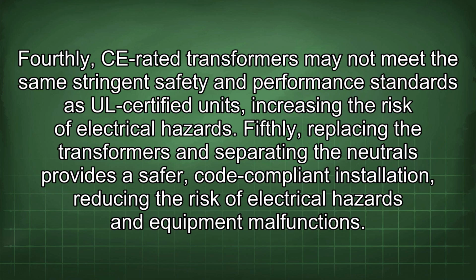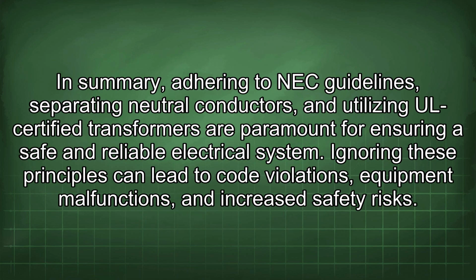Fifthly, replacing the transformers and separating the neutrals provides a safer, code-compliant installation, reducing the risk of electrical hazards and equipment malfunctions. In summary, adhering to NEC guidelines, separating neutral conductors, and utilizing UL-certified transformers are paramount for ensuring a safe and reliable electrical system. Ignoring these principles can lead to code violations, equipment malfunctions, and increased safety risks.